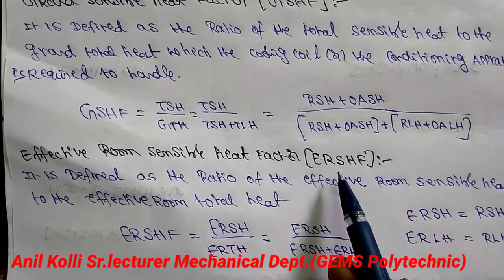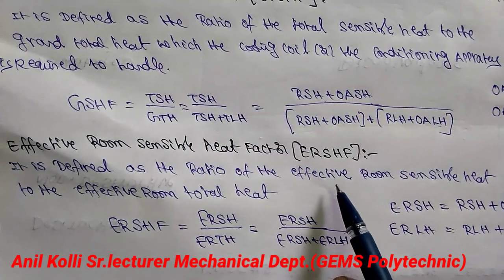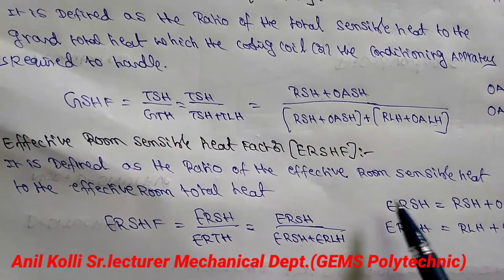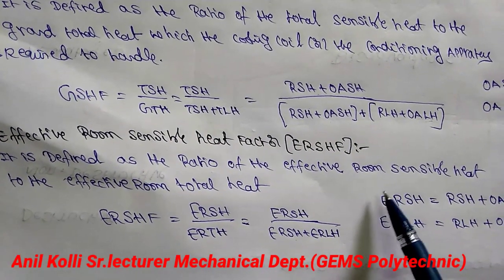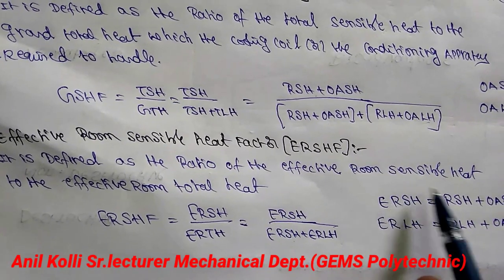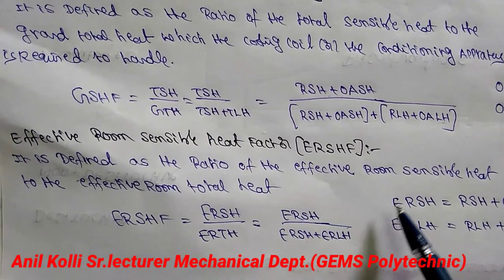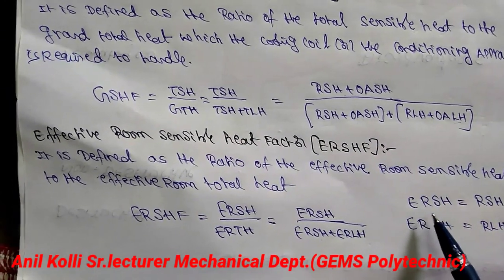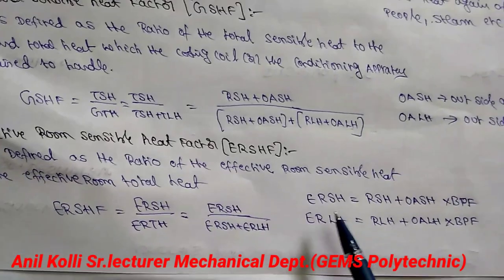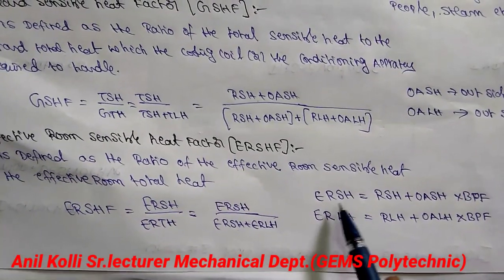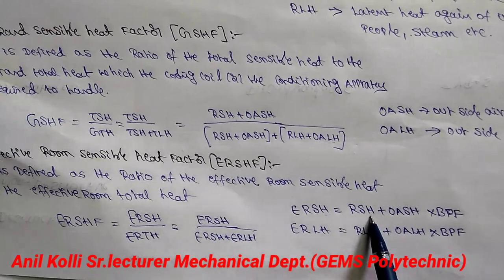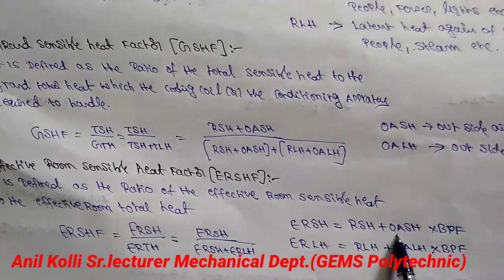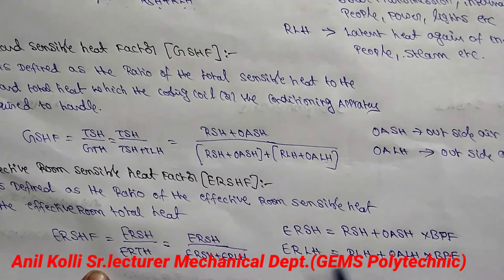Next is effective room sensible heat factor. It is defined as the ratio of effective room sensible heat to the effective room total heat. Effective room total heat equals effective room sensible heat plus effective room latent heat. ERSH is calculated as: RSH (room sensible heat) plus OASH (outside air sensible heat) multiplied by the bypass factor.